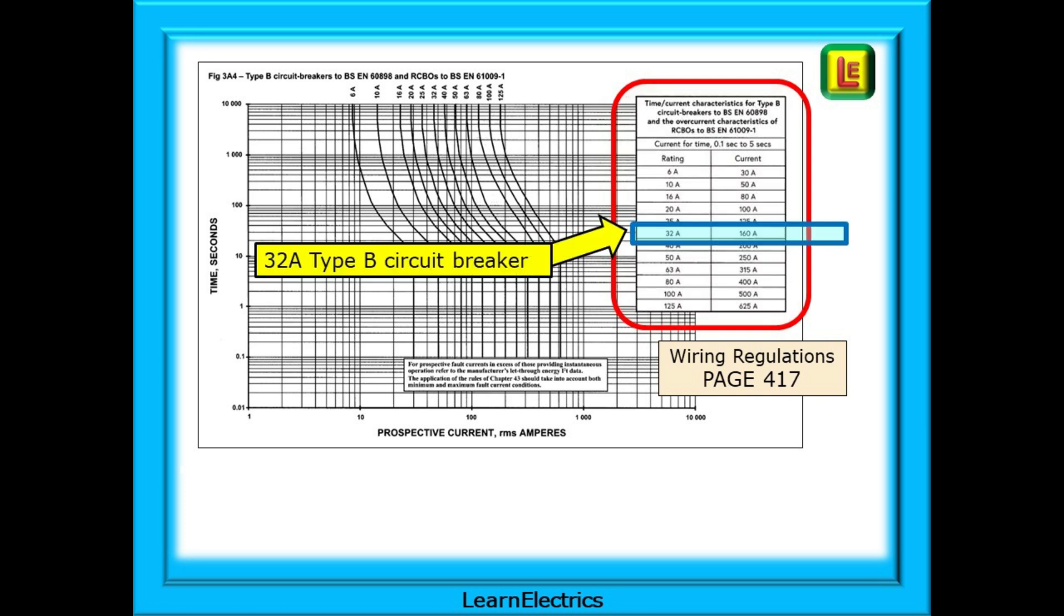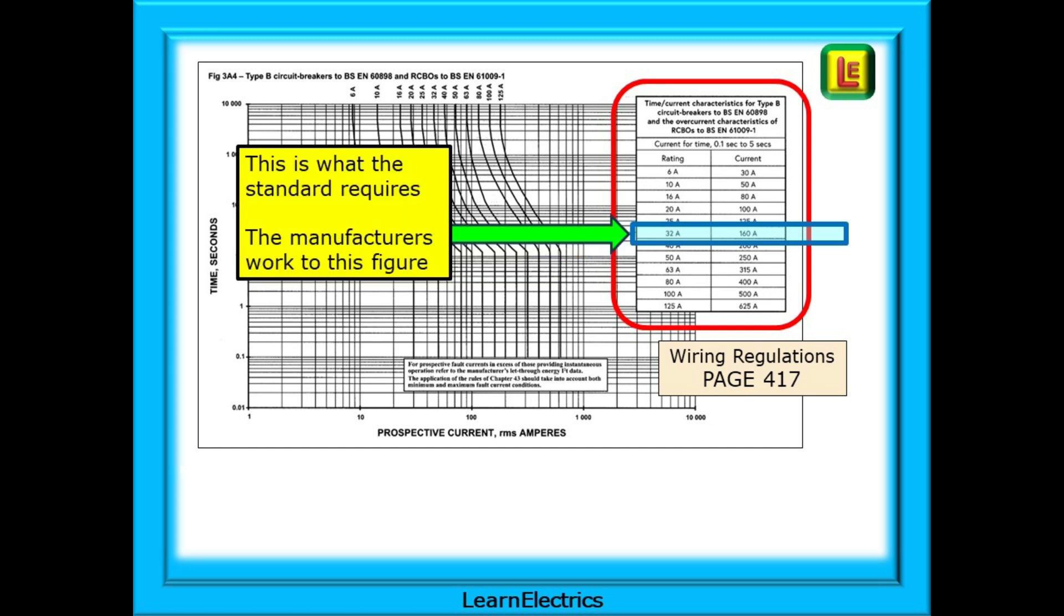Let's follow the ZS story for a 32 amp type B circuit breaker as shown here. This tells us that a 32 amp breaker with 160 amps of fault current flowing through it will trip in about 0.1 seconds. This clearly covers our requirement for the circuit to disconnect in 0.4 seconds or less for final circuits. If it trips in 0.1 seconds then it will also meet the five seconds or less disconnection time for distribution circuits.